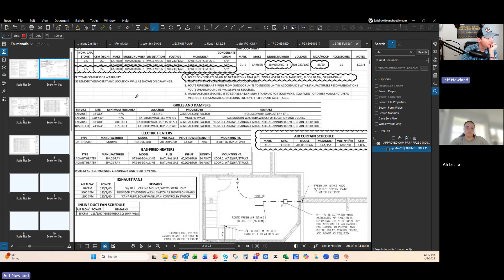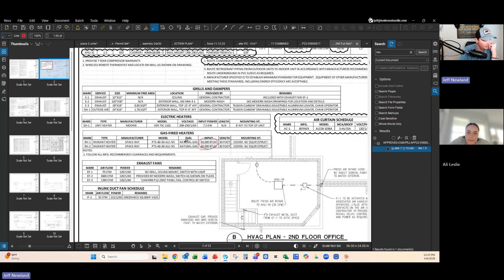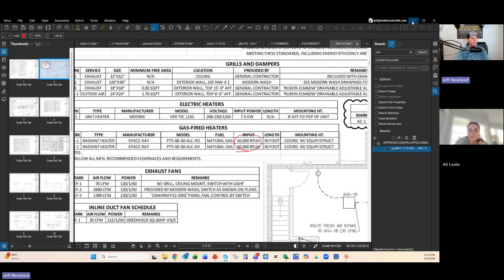So if we look here in our schedule right there, that's what you would look for to give the gas company, 60,000 BTU, and those are for the gas-fired heaters. We had an electrical heater, so there's no BTU there. But actually we would need it rated for 120, because that would be both of them combined. So you add up whatever it is and do it together.